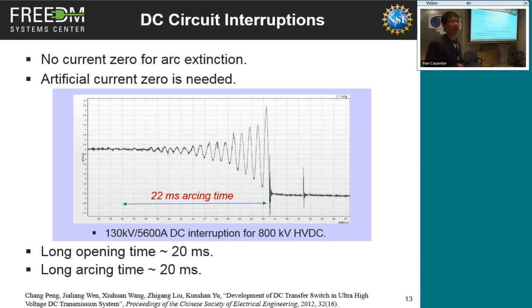Okay, we talked about the condition needed to interrupt the circuit and extinguish an arc, and that is you will need a current zero. In a DC system, you don't have this. And what happens is, there's no natural current zero, and you need to create some. So you can create some artificial current zero. This is what I did a few years ago before I joined here. I designed a DC transfer switch in China, April. I designed a 130 kilovolt, 5,600 amp DC transfer switch for HVDC transmission.